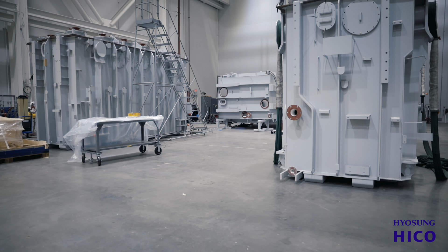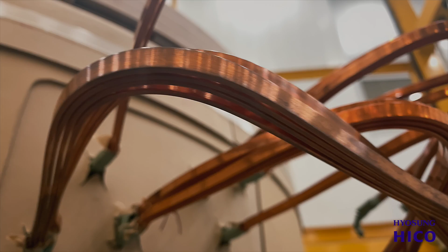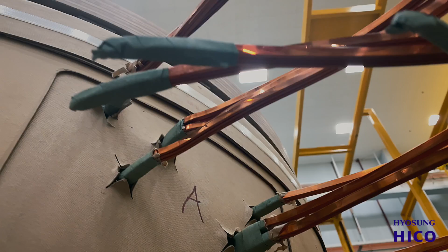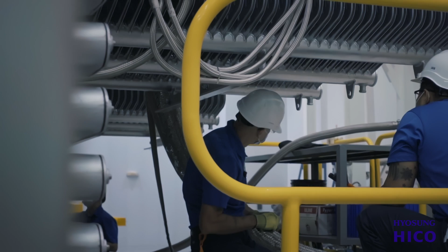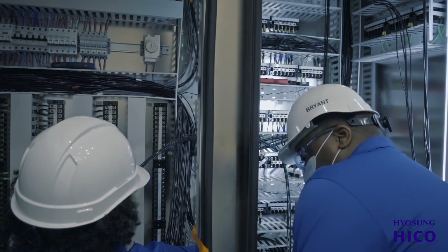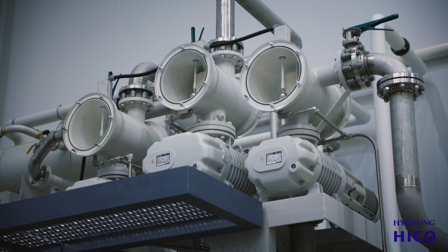Once the upper tank comes in from the weld shop, the core and coil assembly is attached to it, and the transformer begins taking shape with all the internal connections being made. Once the lead assemblies and internal connections are made, it's lifted into the lower tank, where it's welded through the weld shop. Then we go into external assembly, where all of the ancillary and external devices are attached, such as radiators or coolers, bushings, and other components. It is then oil filled and processed. Once processed, it moves into the test hall.